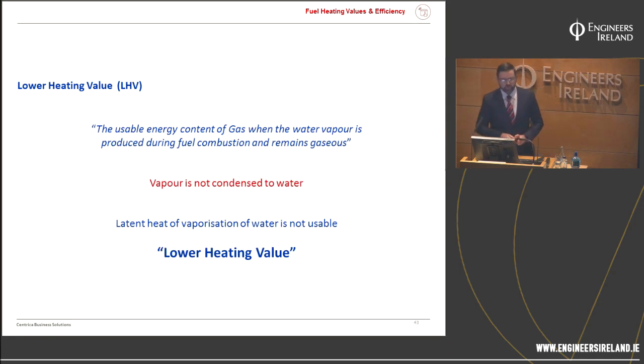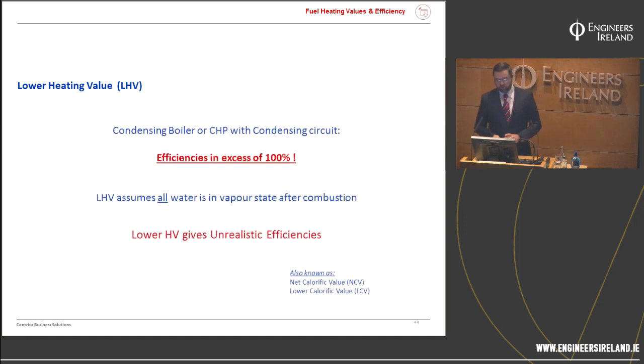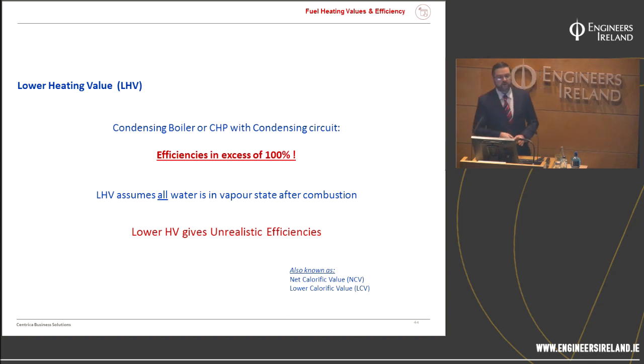Lower heating value - so we're getting back to a bit of thermodynamics. Does everybody remember doing this in college? What we're talking about here is when the vapor is not condensed to water and the latent heat of vaporization of water is not usable. So it's that point in combustion when the gas is ignited and is transforming into vapor and exploding - what amount of water is left? Some people use lower heating value, but if you do that, you're going to end up in a scenario where you may show efficiencies greater than are theoretically possible, so we'd watch out for that.